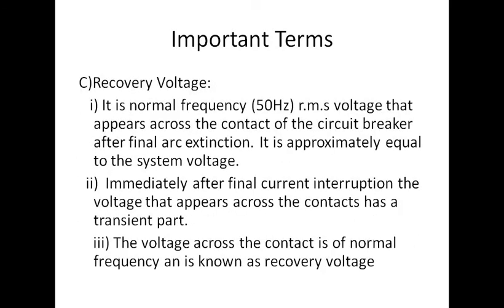The next term is recovery voltage. When the dielectric strength increases sufficiently, the arc is completely extinguished. From the next half cycle, the system voltage will return to normal operation. Recovery voltage is the normal frequency 50 Hz RMS voltage that appears across the contacts of the circuit breaker after final arc extinction. It is approximately equal to the system voltage.